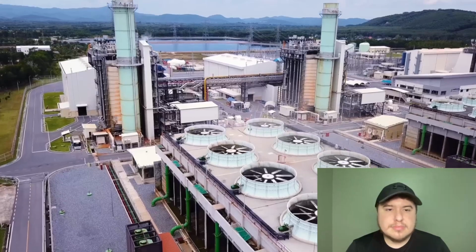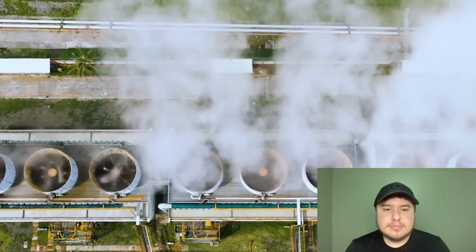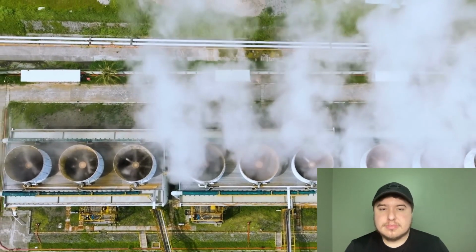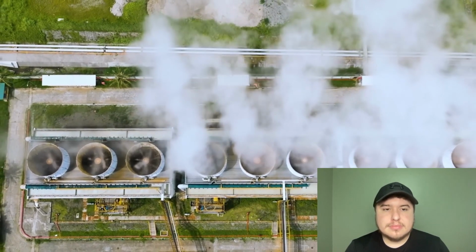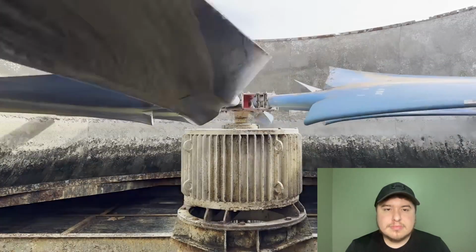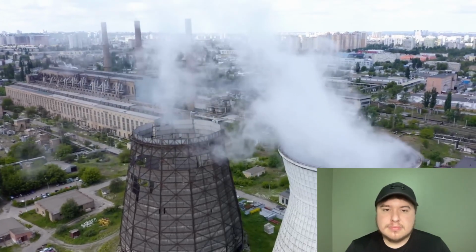And in fact, lots of power plants, refineries, and chemical plants use mechanical draft cooling towers as well. They're less dependent on ambient conditions to create the necessary airflow, they're smaller, usually less expensive to build, and offer some flexibility if heat loads fluctuate. And not all cooling towers use evaporative methods. Dry cooling towers just use heat exchangers inside with the cooling water flowing in a closed loop. In dry systems, you're limited by the higher dry bulb temperature instead of wet bulb, but you don't lose any water to evaporation, and you don't have to deal with the buildup of minerals that happens in wet systems as cooling water evaporates away.